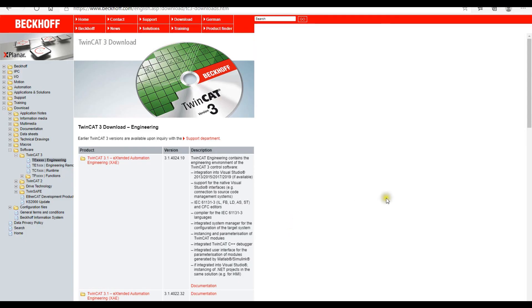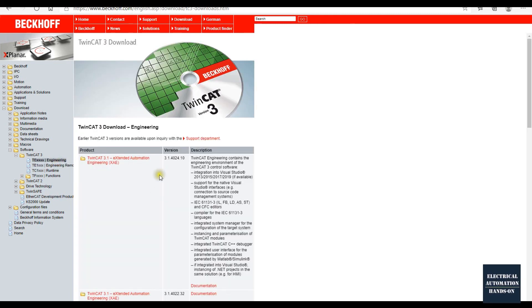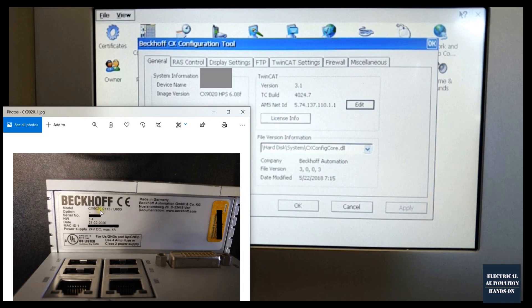To summarize: if your hardware and software versions don't match, there are two ways to resolve it. First, install the Remote Manager and install the old version that matches your hardware controller firmware. Second, upgrade your hardware firmware — especially in the case where you've programmed your project using the latest TwinCAT 3 software and then receive a controller with an old firmware image. In my case, my CX9020 was version 4022 and after the upgrade it became version 4024, matching my TwinCAT 3 software.